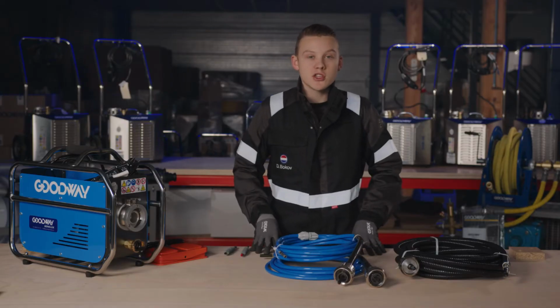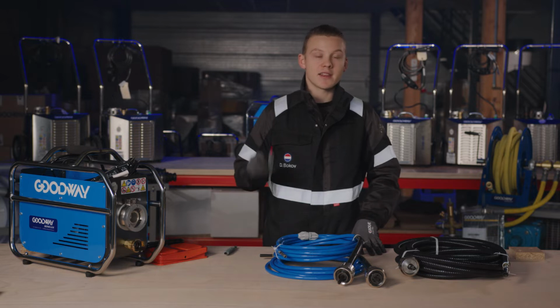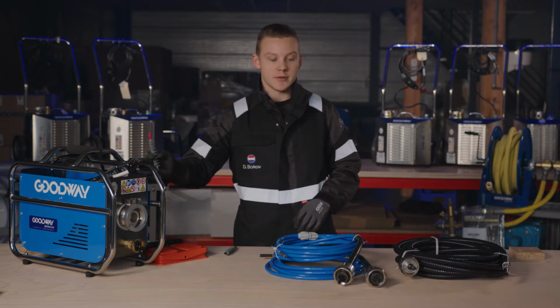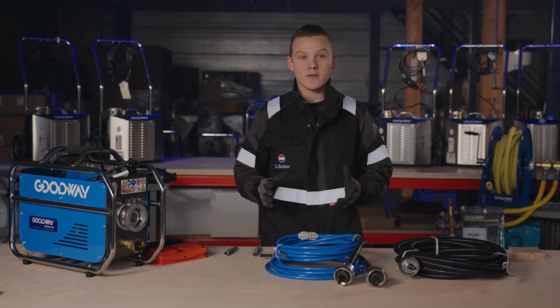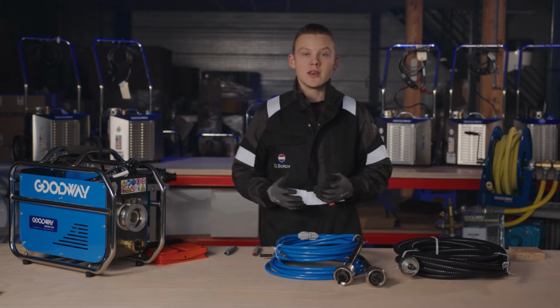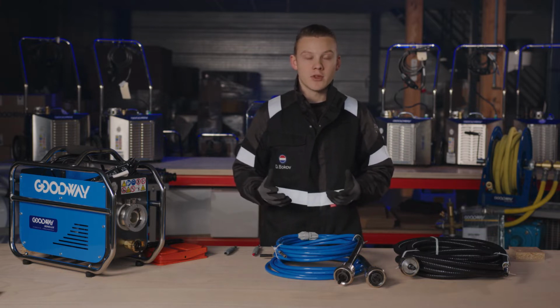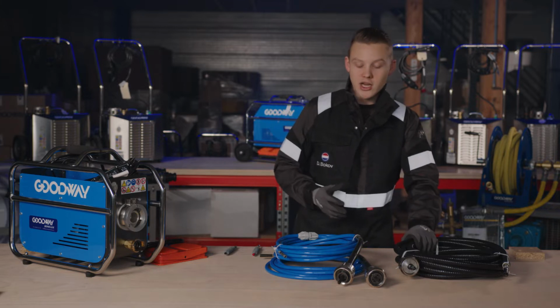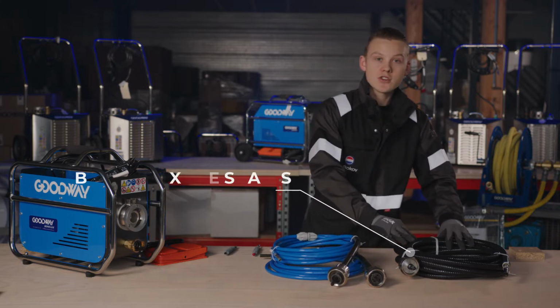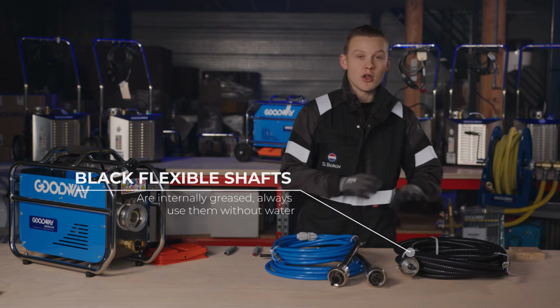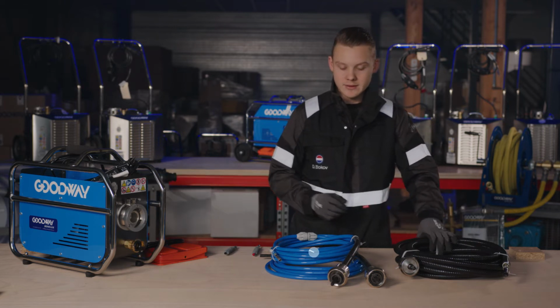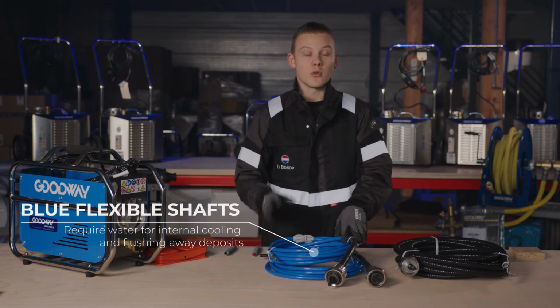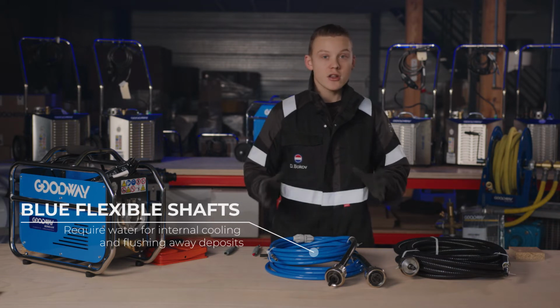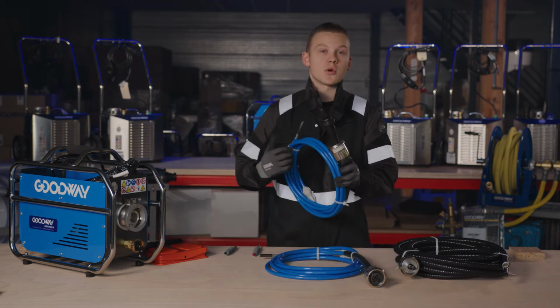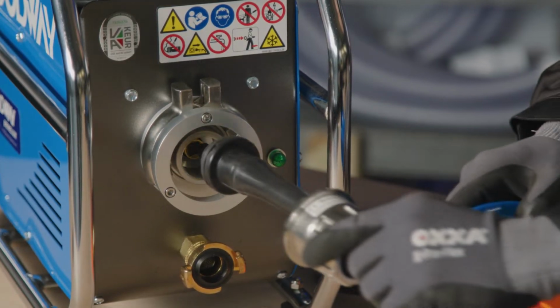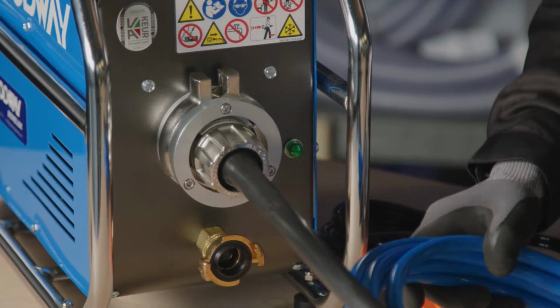Flexible shafts are essential for the tube cleaning process, since they make the connection between the brush and the machine. There are different types of shafts, different lengths, different diameters. This all depends on your application. Normally we supply either a black shaft or a blue shaft. Black shafts are used for industrial applications where no water is used or required. Blue shafts, on the other hand, work with a water flush only. Regardless of the type, all shafts feature a quick connect coupling, which allows for rapid connection to the tube cleaning system.